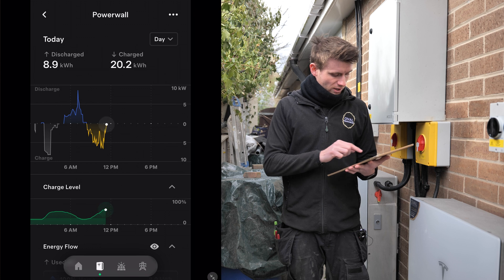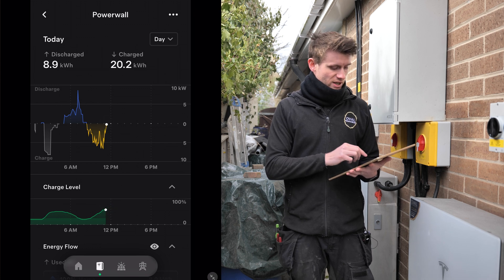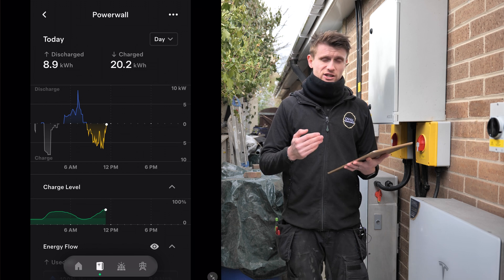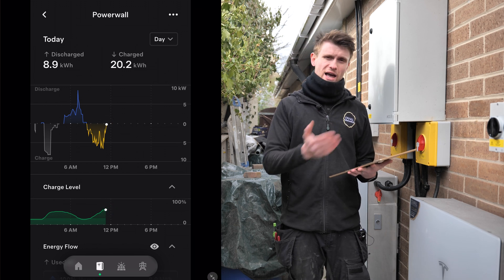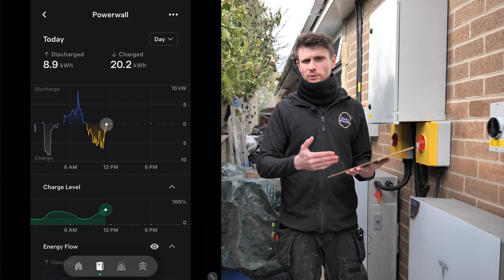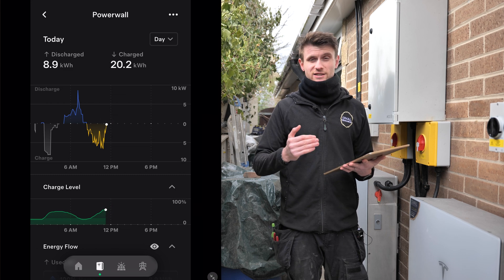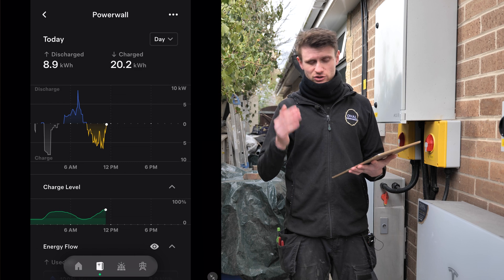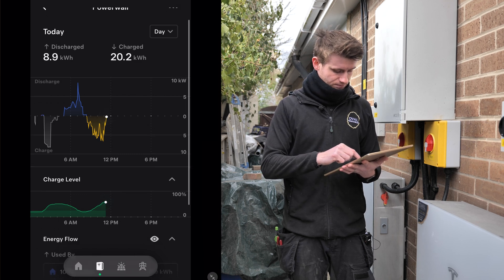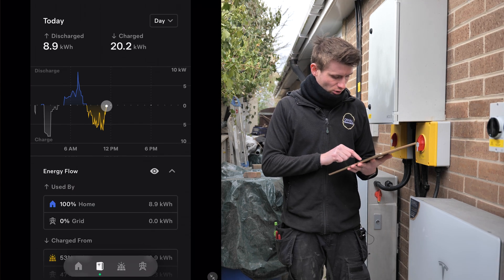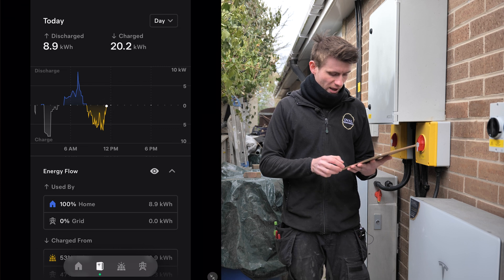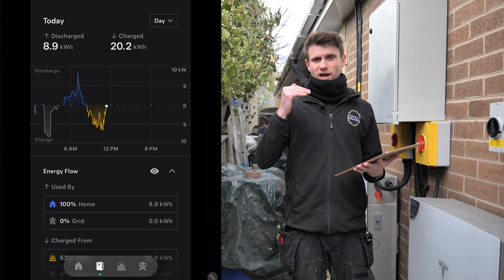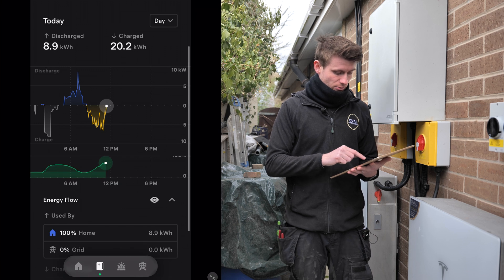We've then got a discharge shown in blue above the line, showing the battery discharging into the house to cover the morning load. The air source heat pump has probably come on to heat the house up, so now the battery is doing its thing - discharging into the house and making sure there's no grid purchase during that period. So 100% of the discharge, 8.9 kilowatt hours, has been used by the home during that early morning period.